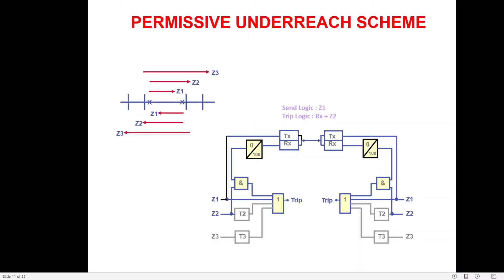In Permissive Under-Reaching Transfer Tripping (PUTT): consider the fault closer to the right-hand bus. The left-hand relay picks up in Zone 2 while the right-hand relay picks up in Zone 1. Because it is an under-reaching scheme, Zone 1 sends the carrier signal. The right-hand relay issues a trip command and sends the carrier to the left-hand end. Here, unlike in Direct Transfer Tripping, the carrier is not connected directly to tripping — instead it goes through an AND gate that checks Zone 2 pickup.